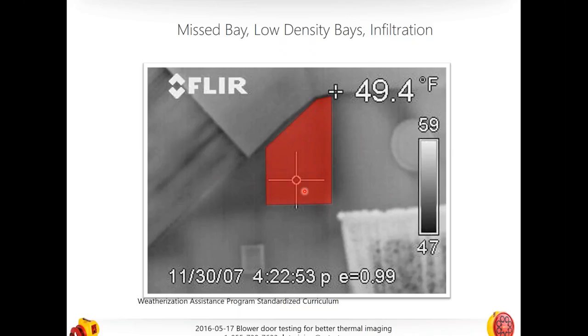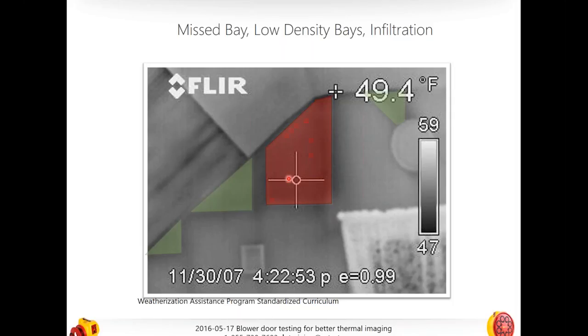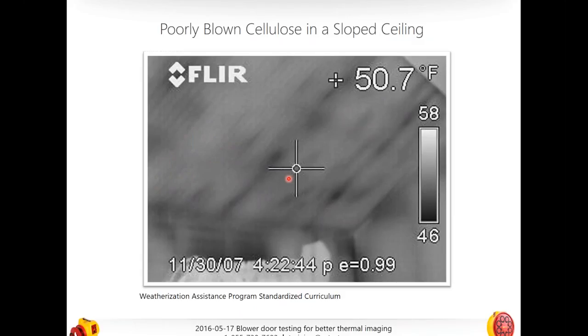Here's another example of a Cape Cod problem. We have a slope ceiling and gable walls as exterior walls, with a darker spot on an end wall with a window. The drywall has been installed over original plaster and lath on the ceiling. You can see air coming down through behind it. The darkest areas indicate an empty wall bay — completely empty — while lighter shades indicate partially insulated bays, with air visibly moving through.